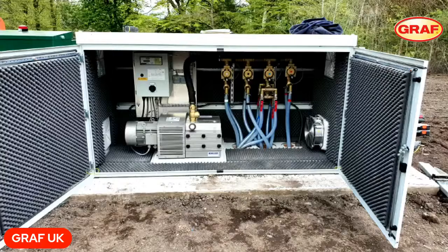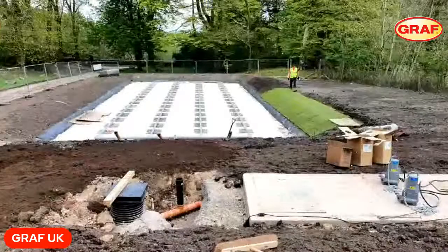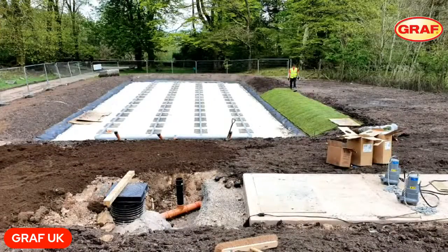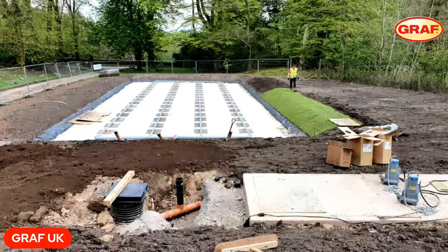And then we've also got images of the reed bed. Correct me if I'm wrong. Yes, you're correct. Tertiary treatment. Yes, exactly. So the system itself is discharging into a pump station, and that pump station is set on a timer to lift the treated effluent water up into a final reed bed system. So you can see the reed bed now. That'll of course grow up over time, and add a tertiary layer of treatment to the effluent water. So we've got a very, very good final quality of effluent.